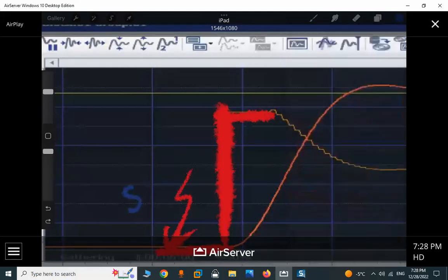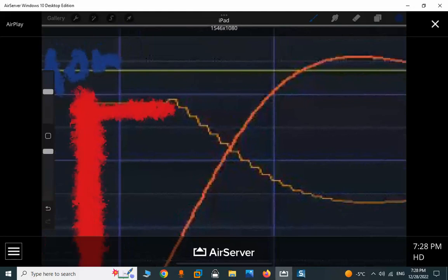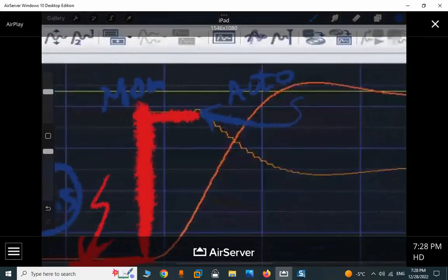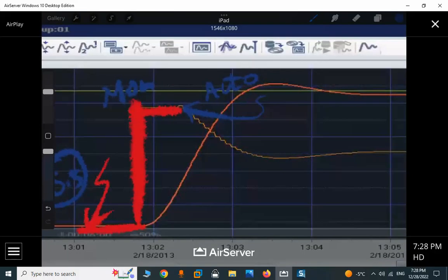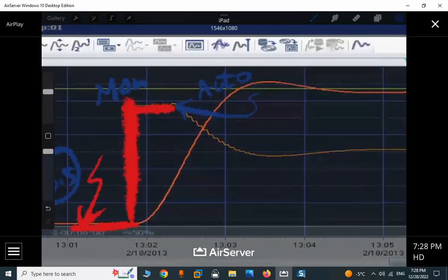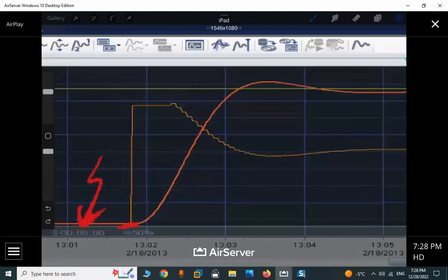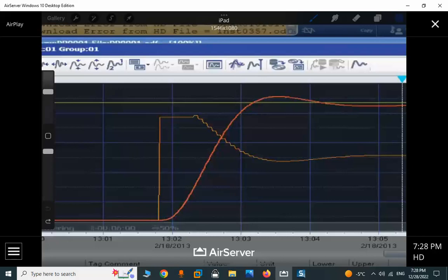Here is a steady state. PID in here is in manual, and automatically by the Sequence program, we put the PID in auto mode here. So we find the reaction curve based on the actual process model. We gather all the data needed and feed all those data to the offline tuner, and the offline tuner will provide us with the estimated model.